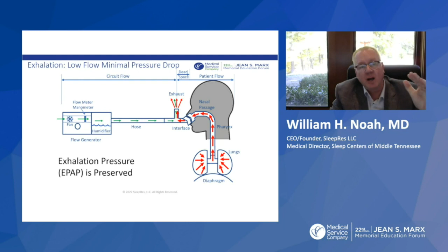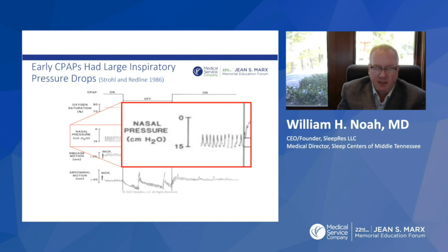Now this is a study from Kingman Strohl and Susan Redline. Dr. Redline was actually, I think, a fellow with him at this time at Case Western in '86. Of course, you all know she's at Harvard and just gave the keynote address this year at APSS. So this is a study they did with first generation Philips CPAP, actually Respironics at that time, in 1986. And look over here on the left, you can see that the patient was on 14 centimeters, but these first generation machines couldn't adapt the motor speed quickly enough. And so when they breathe in, look, the pressure drops. Now the arrow's been going up, but the pressure is reducing on inspiration, down to about 7 or 8 centimeters. So they're at 14 on expiration, but only 7 or 8 on inspiration. And of course, the point to see about this is the fact that they didn't have any respiratory events.